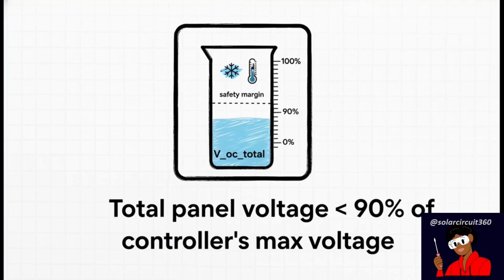Before we jump into that list, there's one golden rule you absolutely need to know: the 90% safety rule. Your total open circuit voltage, listed as VOC on your panel spec sheet, should never be more than 90% of your charge controller's max voltage limit.